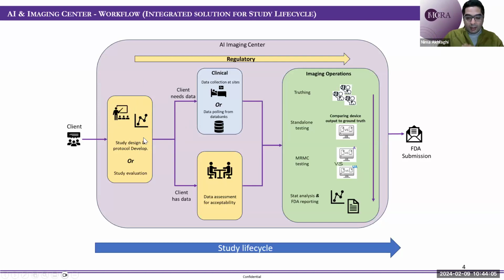And of course, the performance testing document is one of the key documents that you have to put as part of your FDA submission. A lot of the decisions that FDA is going to make are going to be around this performance testing and assessment. So after you pass that first step of the study design, and you have the study protocol, you know the type of data you're looking for, the subgroups, the sample size, and everything, the next step is, okay, we need the data. As Alex mentioned again, following best practice, one of the key components is to make sure that you have data that's independent from any of your training and internal testing, and that is also representative of your intended patient population as you're claiming.